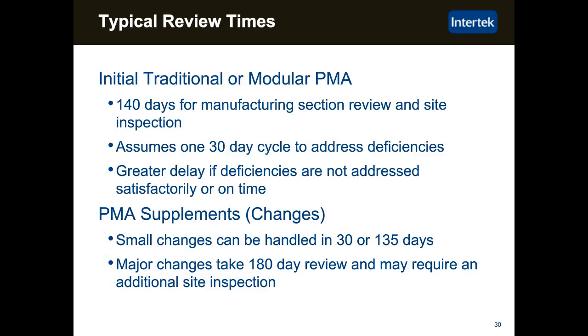The FDA also allows you to do what they call a modular PMA, where the manufacturer can provide information in agreed upon increments. As an example, the FDA could review the quality manufacturing system and manufacturing documentation while clinical trials are underway, and then when the clinical evaluation is complete, it can be submitted in a separate module. The fee is required at the start of a modular PMA, so the risk that you have is that if you fail your trials or anything and you had to withdraw, it could be the loss of that PMA fee.